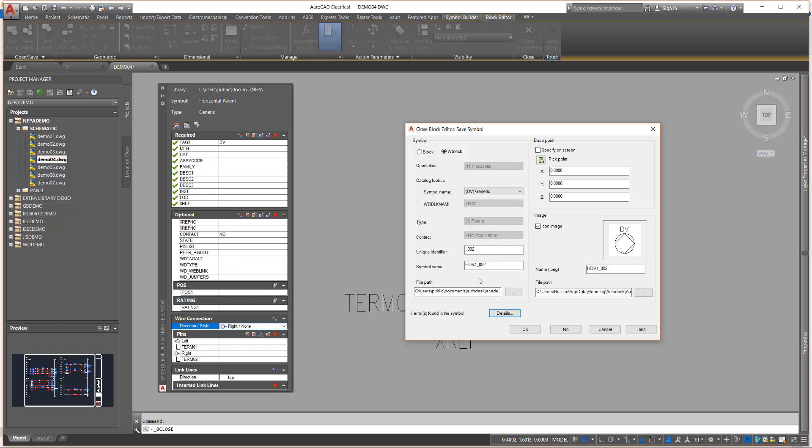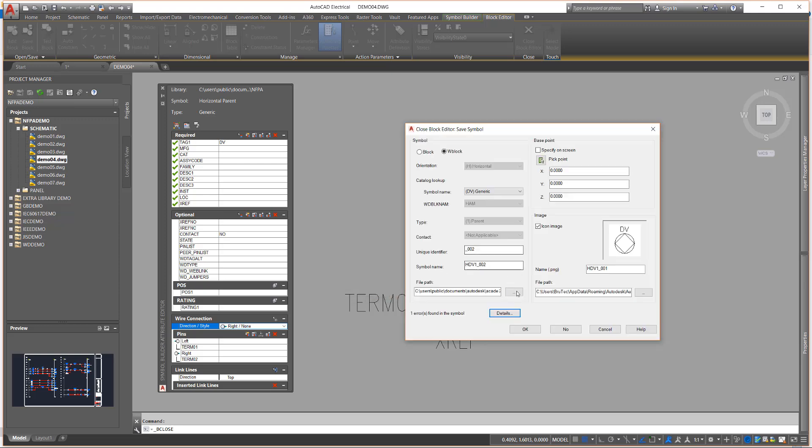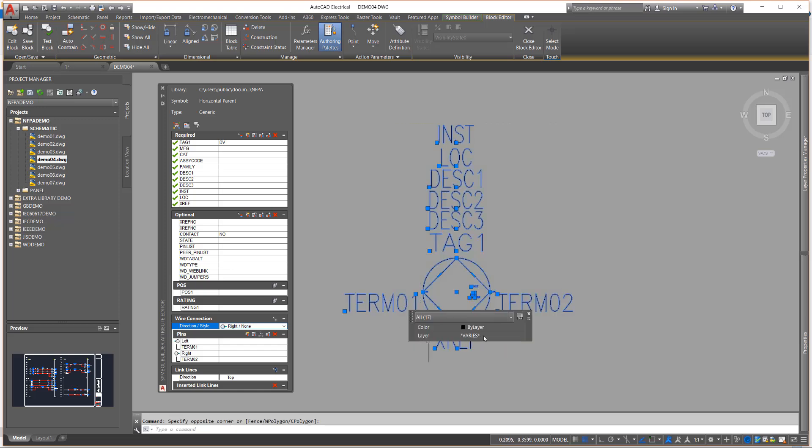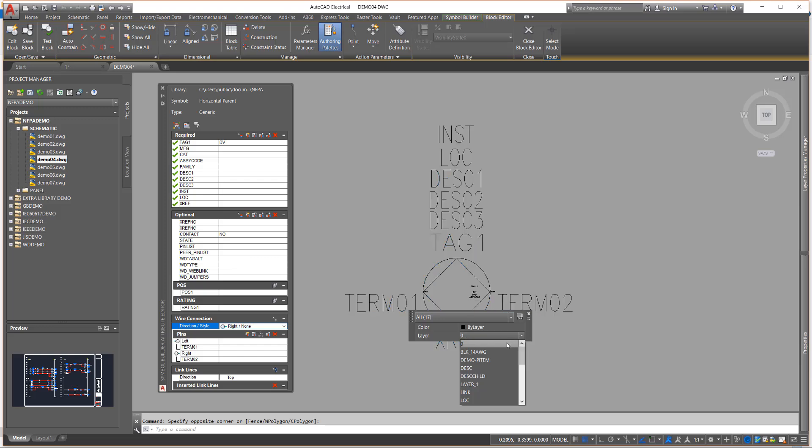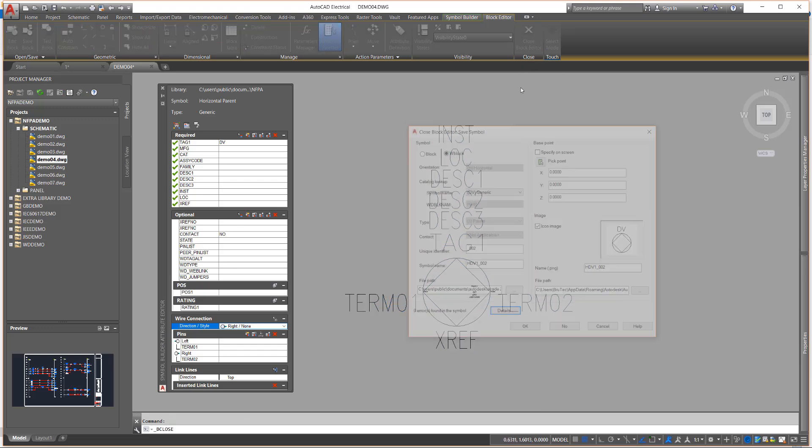This tool automatically names the symbol using the AutoCAD Electrical symbol naming convention and even performs an audit of the symbol. Here we notice that some layers are not correct. AutoCAD Electrical expects all entities to be on the zero layer when creating a symbol. When inserted, the software will move various parts of the symbol to different layers, as determined by the drawing properties.